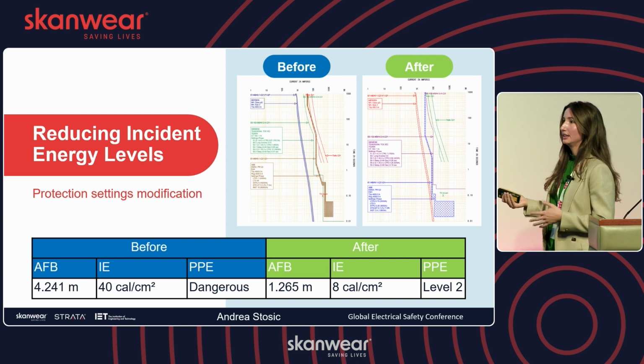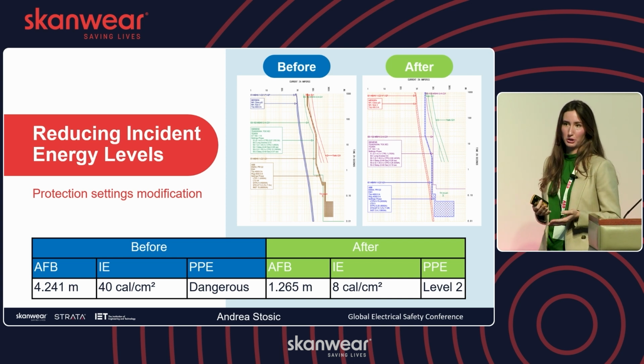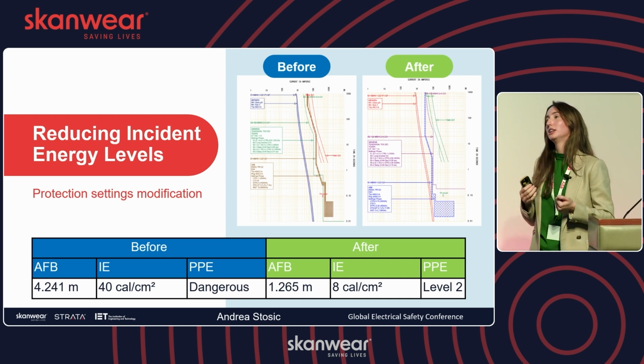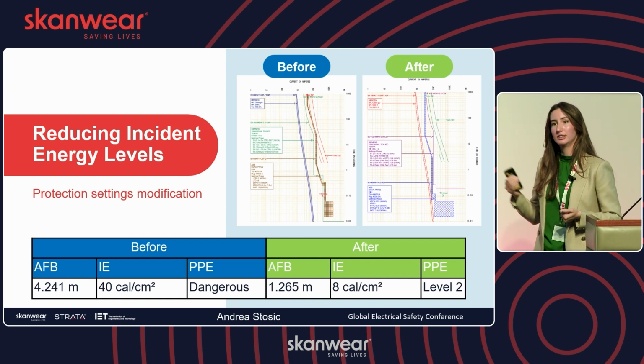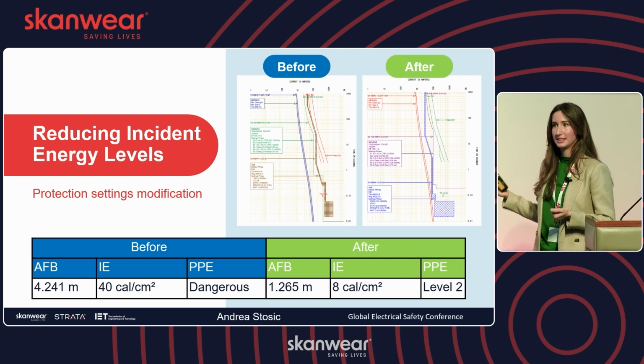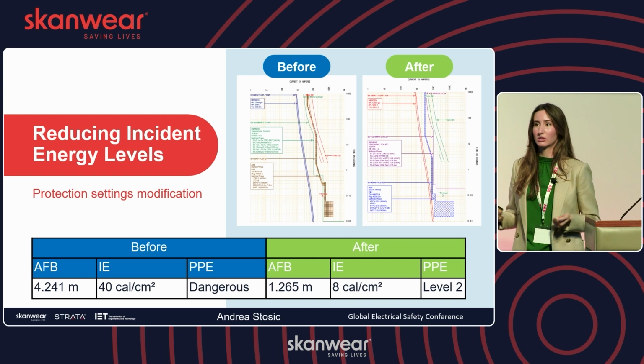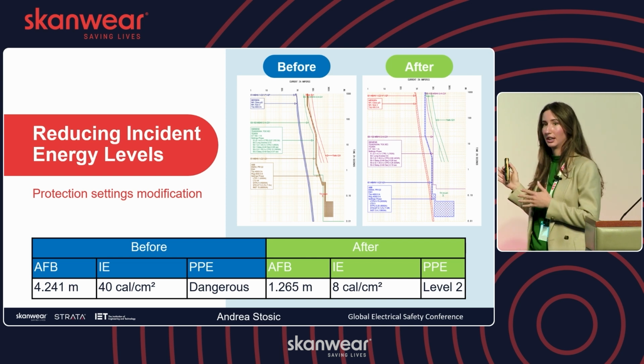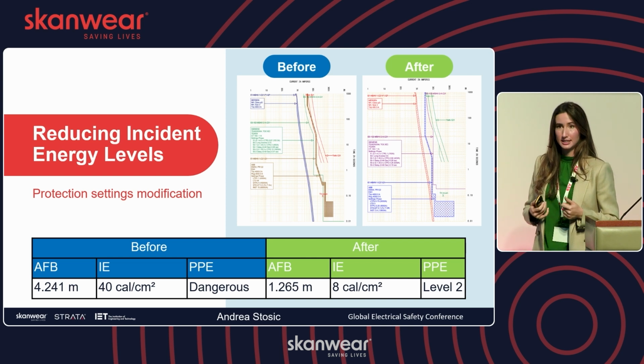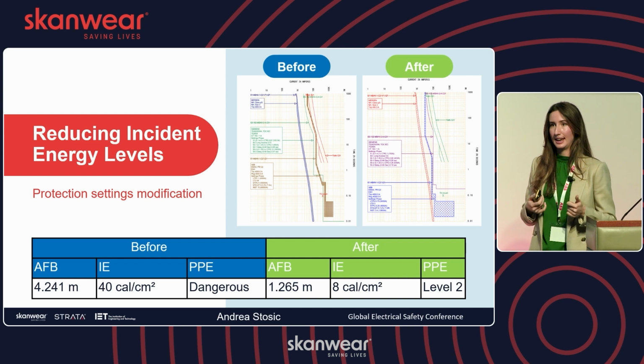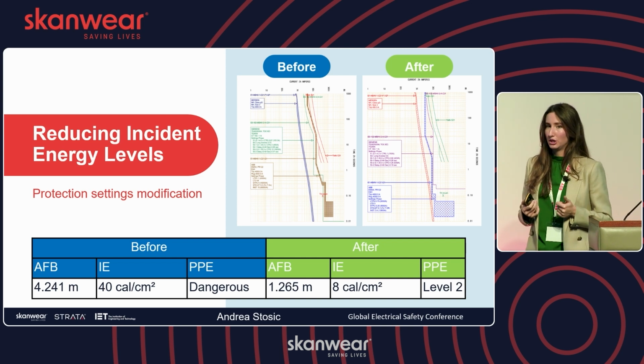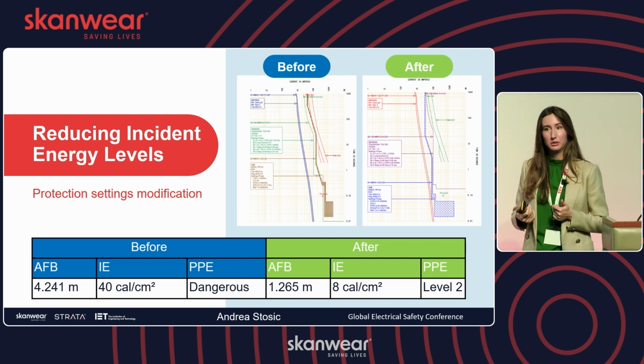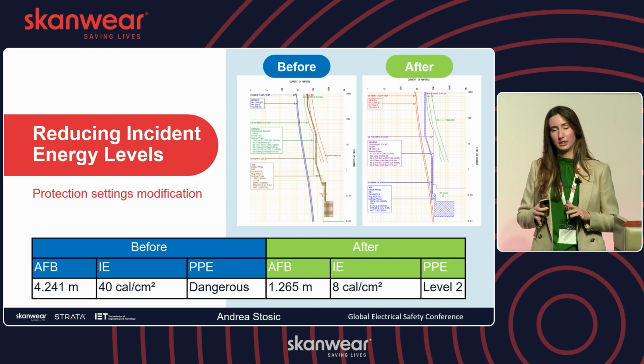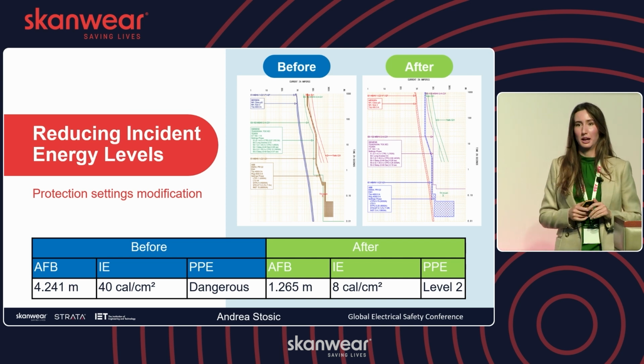And this was a great example, so that's why I want to share it with you and also let you know that this is usually the first step, because this is the simplest step, the quickest step, the most cost-efficient step. So we always start like this. There will be cases where we will change protection settings and perhaps won't achieve the targeted PPE level, but then there are some alternative steps that you can take, and Marcin will talk you through later as well.